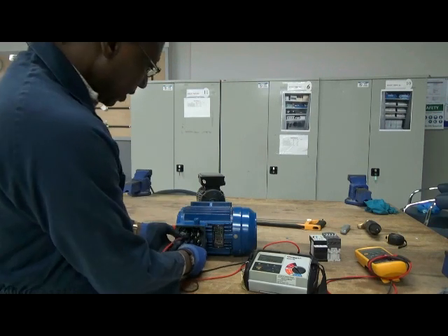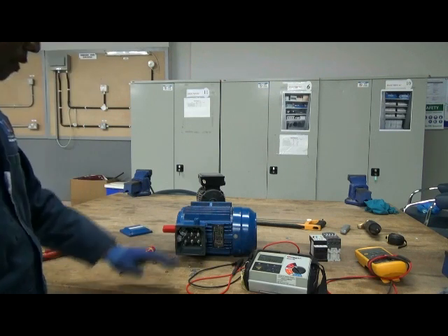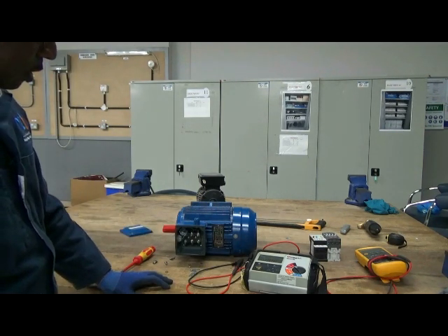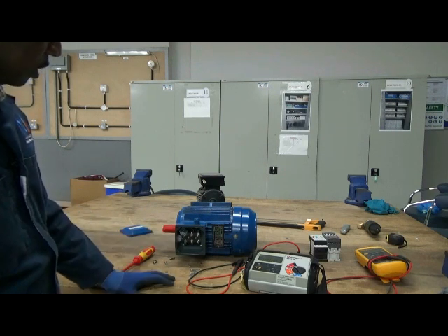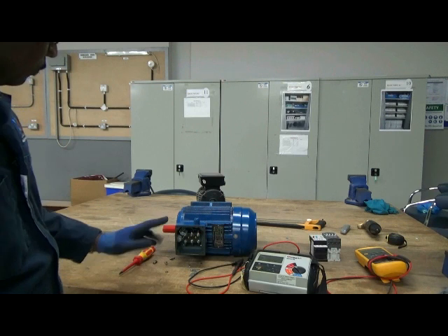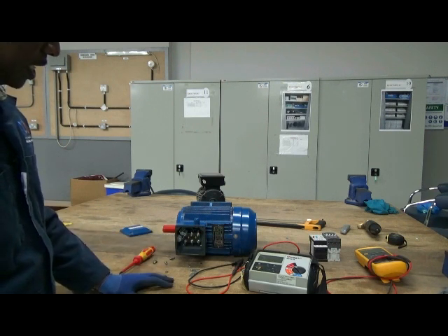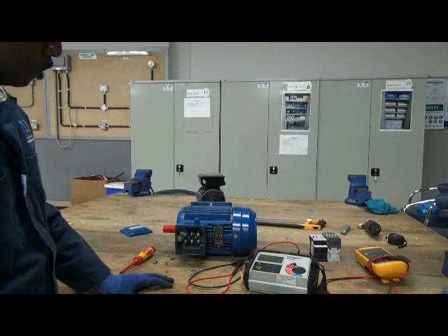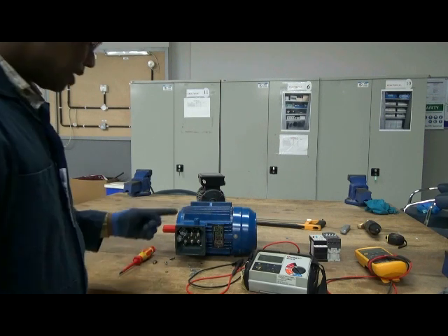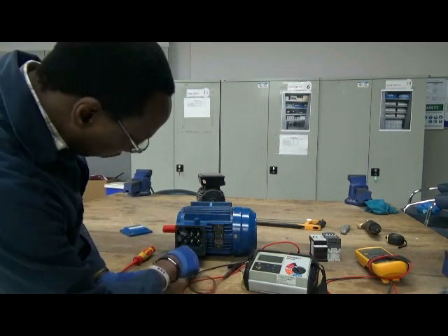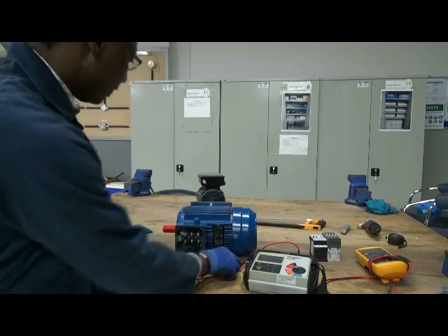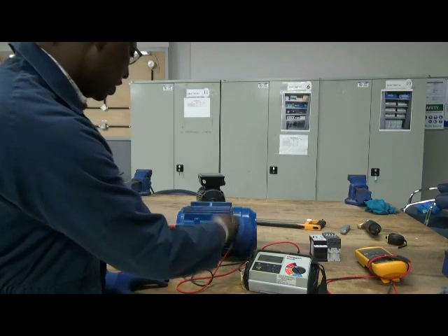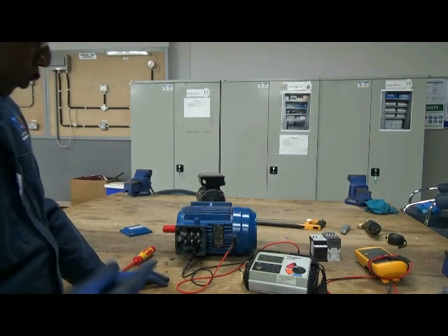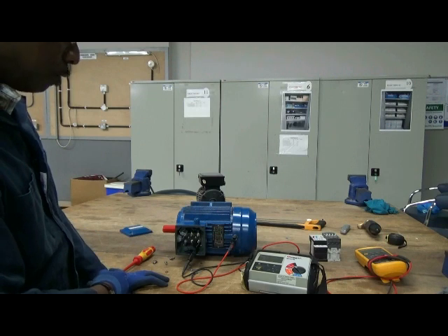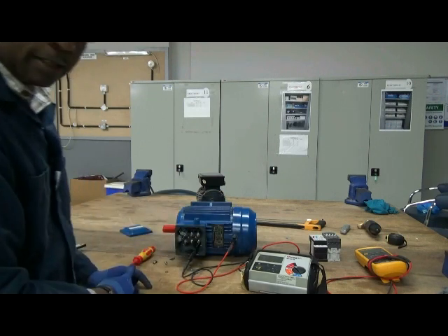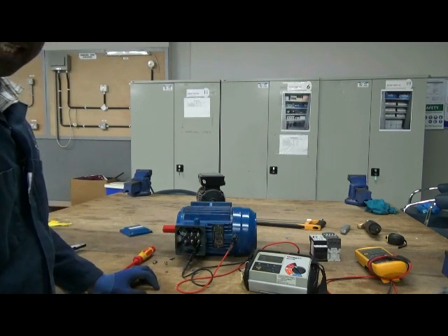So that brings me to the end of this testing. I've tested the resistance of the windings. I've tested the insulation resistance between windings. Now I should do a third test, which is called insulation resistance between windings and earth. So now I'm testing the insulation between all of the windings, one at a time, to earth. The body of the machine can be treated as earth. So I'm going to induce another 1,000 volts between that winding and earth. The insulation resistance again should be greater than 1 mega ohm.